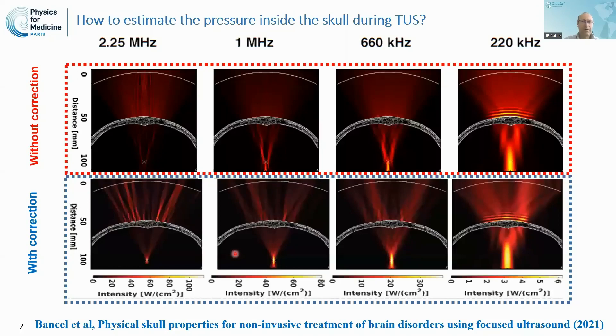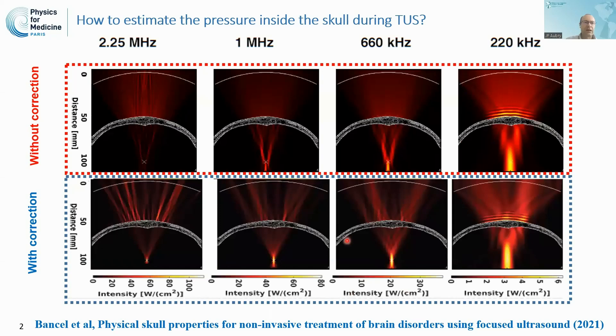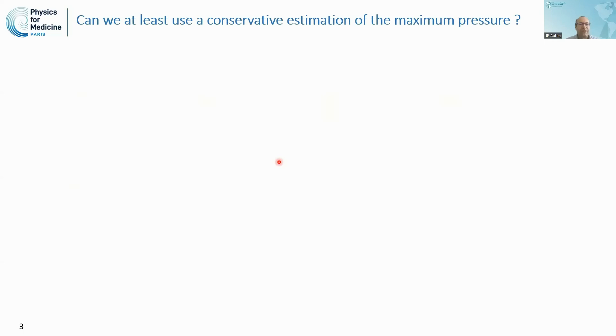We wanted to discuss how to estimate the pressure inside the skull. The pressure inside the skull during transcranial ultrasound depends on the shape of the transducer, the location of the focus, the frequency being used, but also whether you are performing transcranial focusing without correction or with correction. So estimating the pressure field inside the brain is not so simple. We wanted to know if we could use a conservative estimation of the maximum pressure inside the brain.